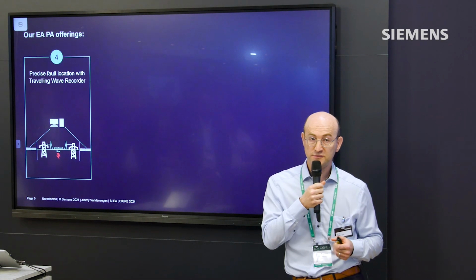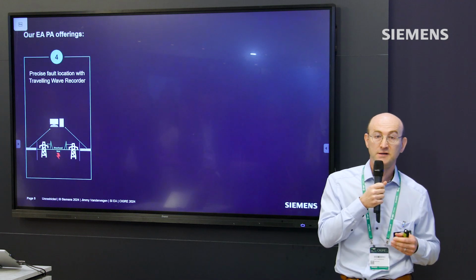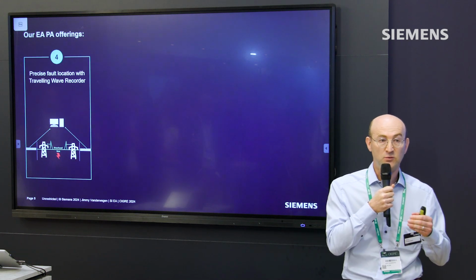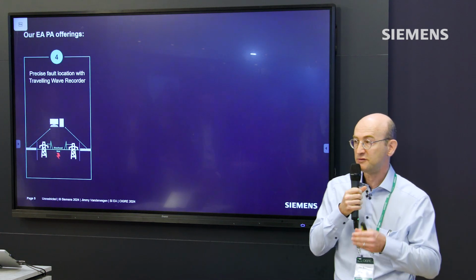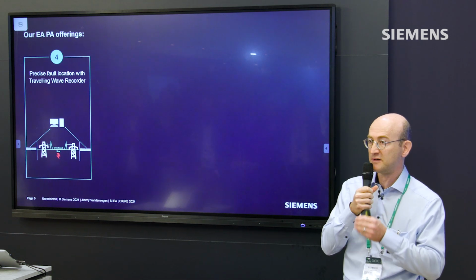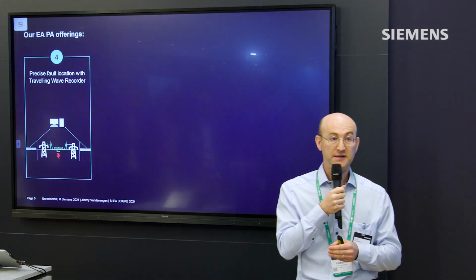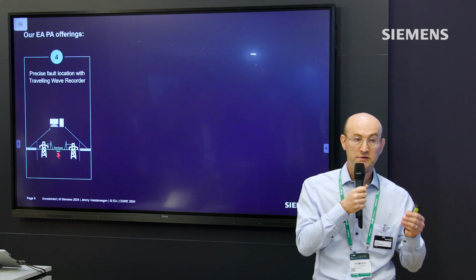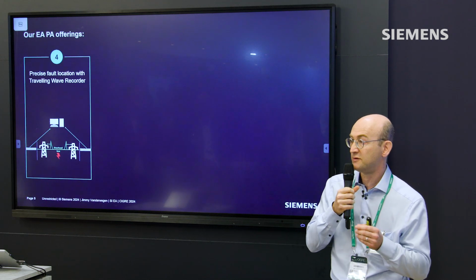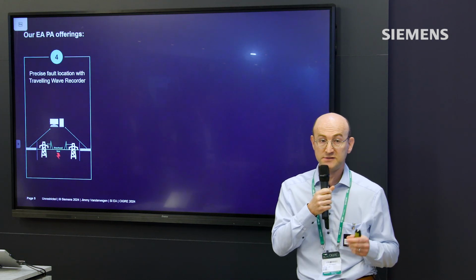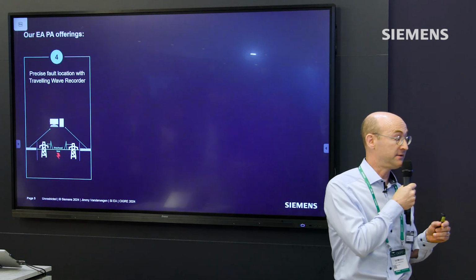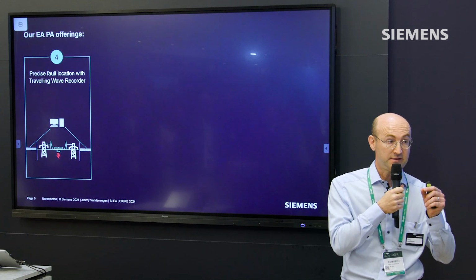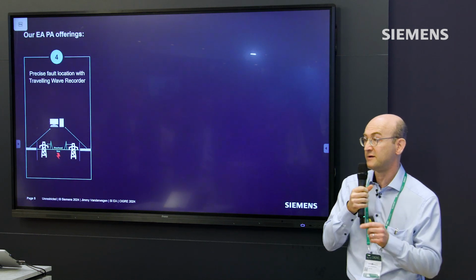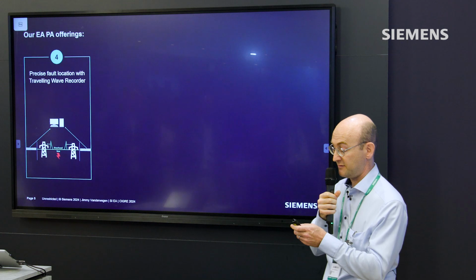The fourth solution uses traveling wave technology for precise fault localization, specifically on very high voltage transmission lines, overhead lines, or cables. The more precisely you can identify the fault, the quicker you can repair the problem.